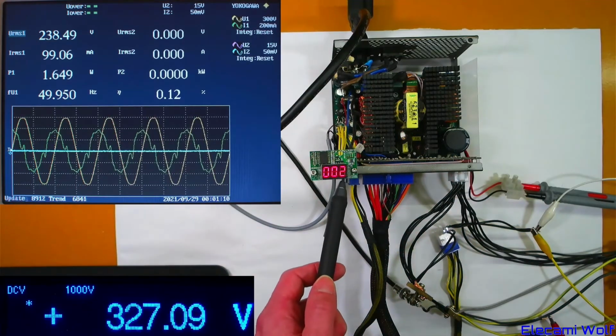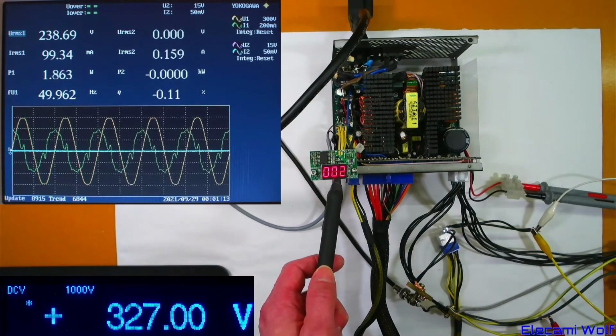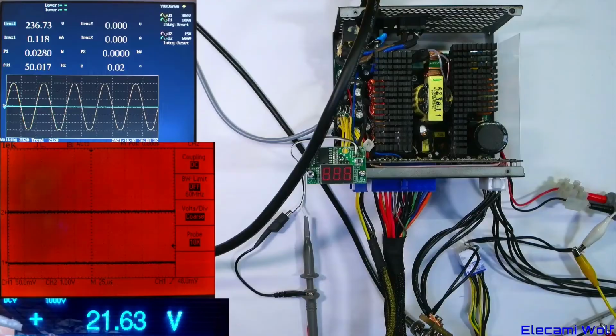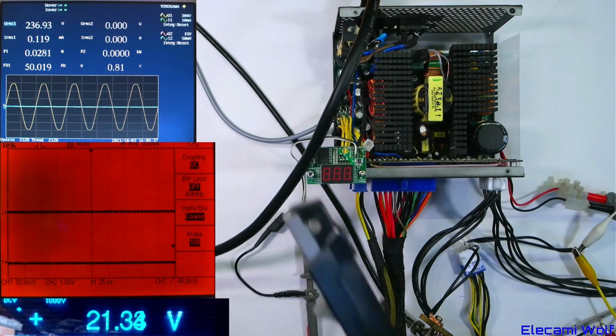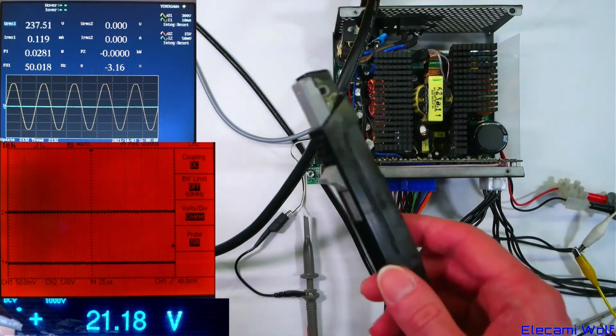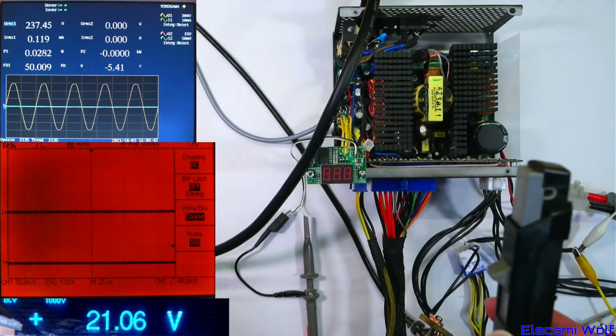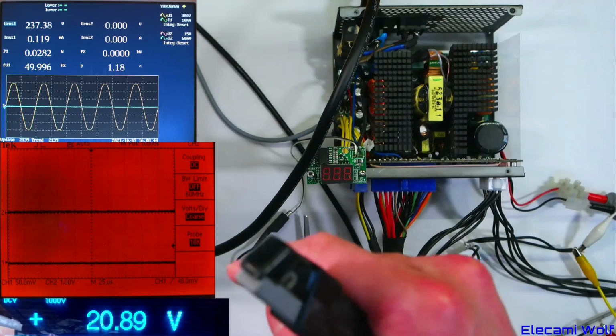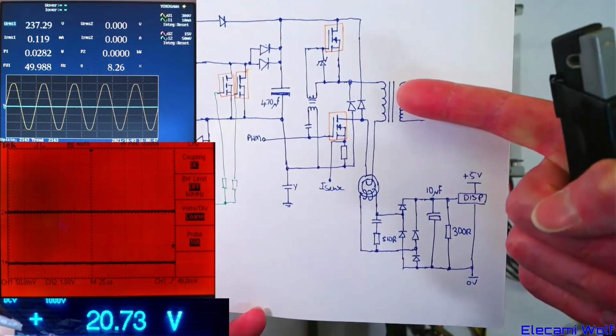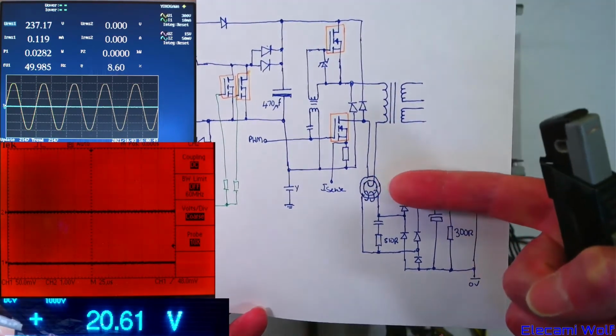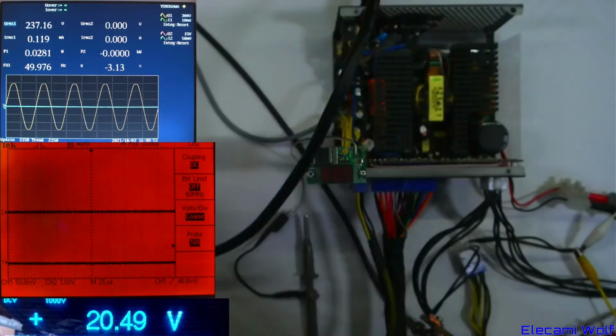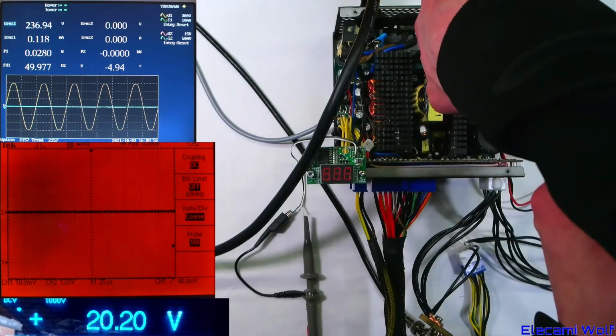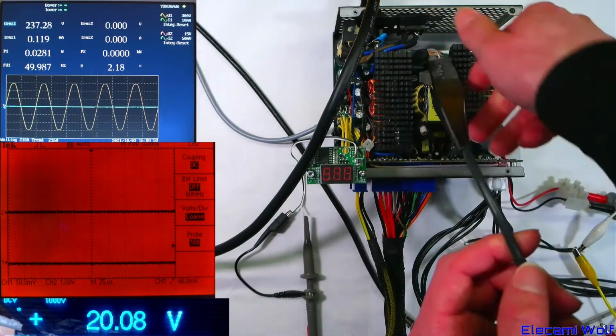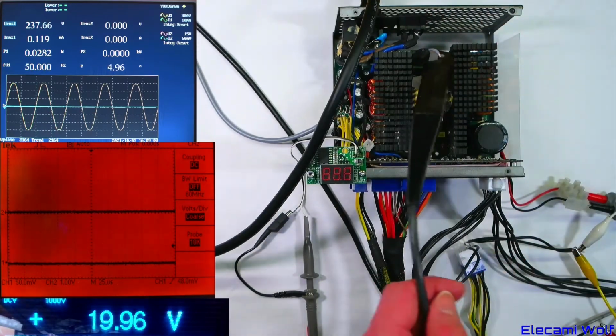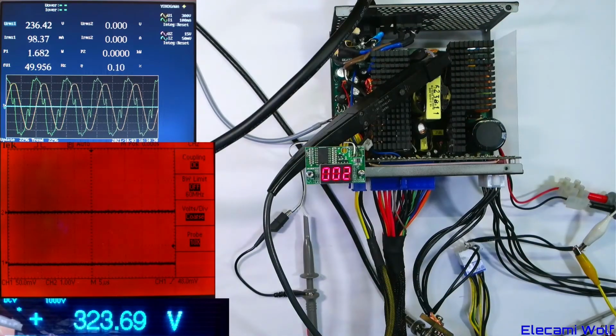The next thing we'll look at is what the signal that gets sent to this power meter looks like. I've got the oscilloscope set up now, you can see there with the red screen. I've got the current probe connected to that on channel 1, set to 1 amp per division. We're going to connect the current probe in series with the primary winding and the CT that measures the power around here. Current clamp wedged in place there.